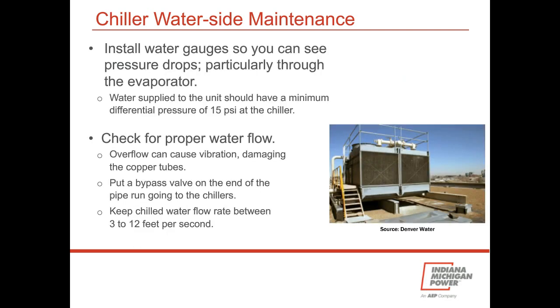It'd be nice if you could measure pressure drops through the water loops. Typically, you're shooting for about a 15 psi differential through the water loops, and then keep chilled water flow rate between 3 to 12 feet per second, kind of a ballpark target there.